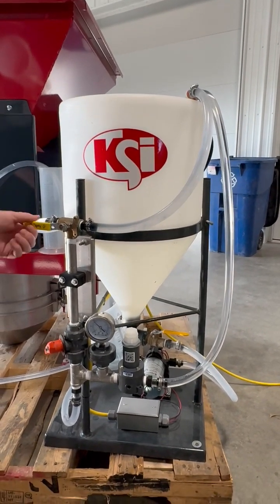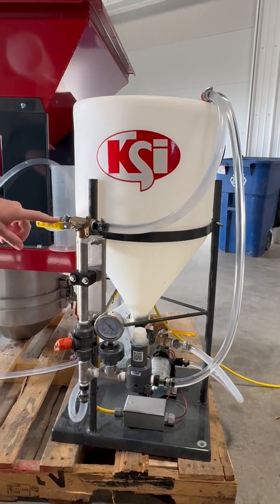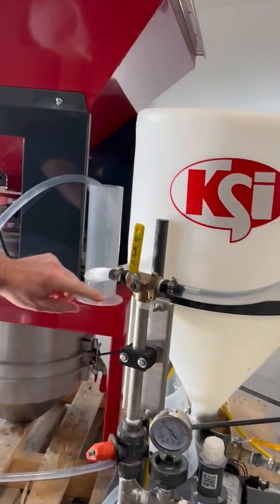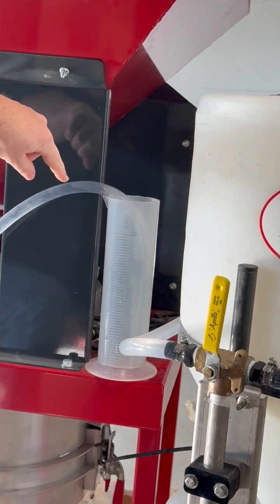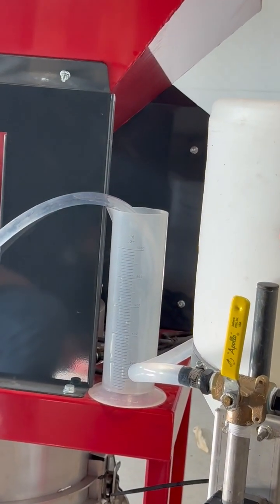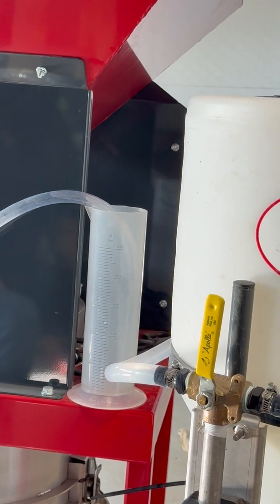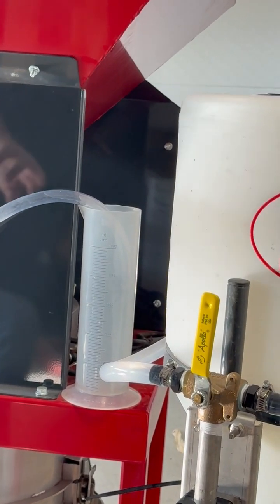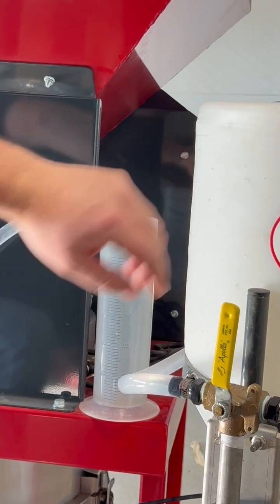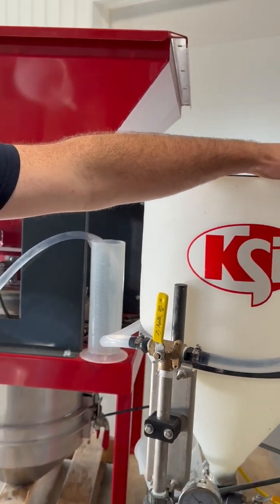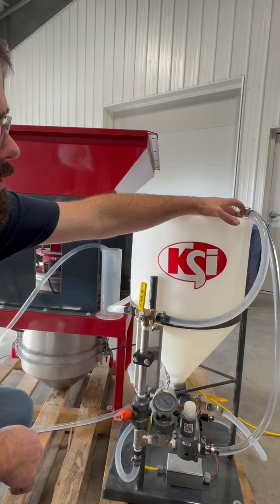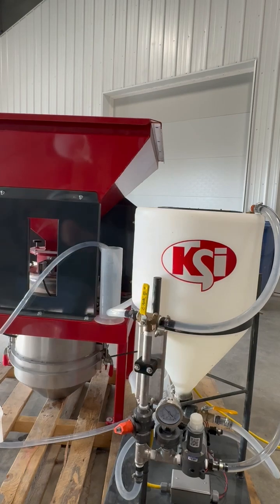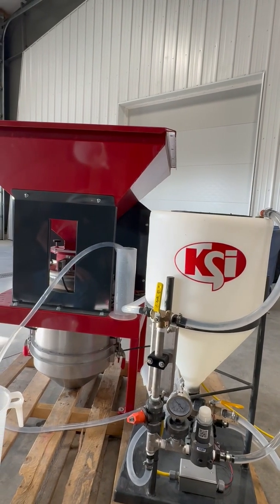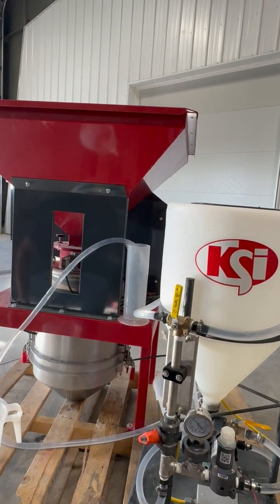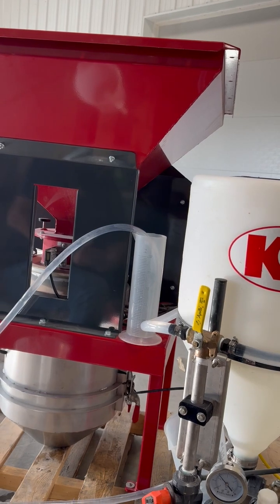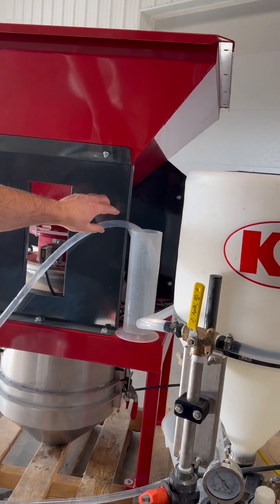So at this point, I'm going to go ahead and send the treatment to the treater line, which is where I'm catching, in this case, the treatment or water for calibration. In the field, you might be using this line right here. You'll just disconnect this line and do your calibrations through that. So, can you pull that line up so you can see the flow going into the?